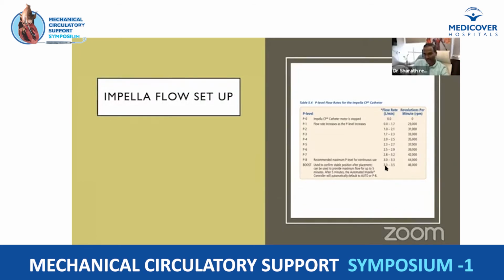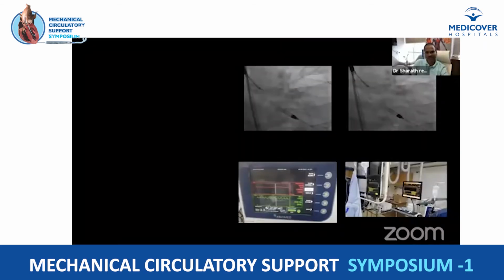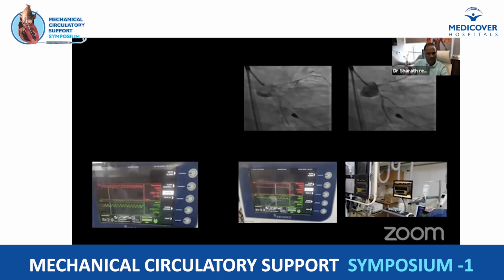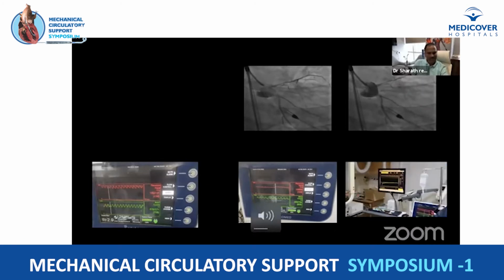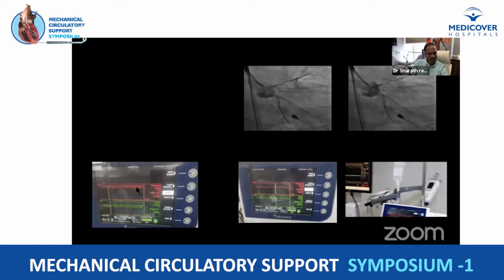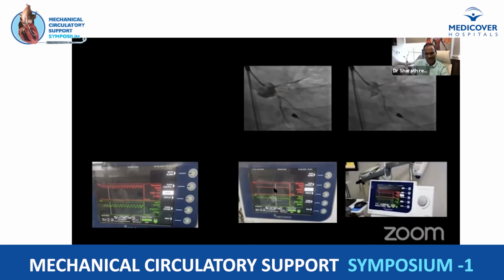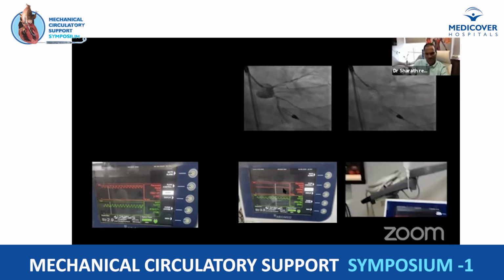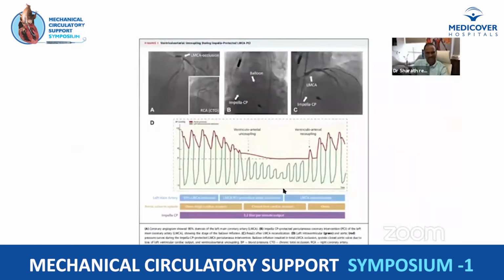So this is the flow pattern which you will get with prefixed flow rates in the Impella CP catheter. A boost is where you go to the maximal flow which can be achieved in that patient, and which stays for 5 minutes. To show you an example, in this case, while doing LMCA bifurcation angioplasty, the patient just went into no flow for a brief period of time. What exactly happened is, you can see this is the normal aortic pressure wave, and here there is a complete loss of pressure wave. There is no pressure wave of the aorta, which says ventricular arterial uncoupling in this situation.